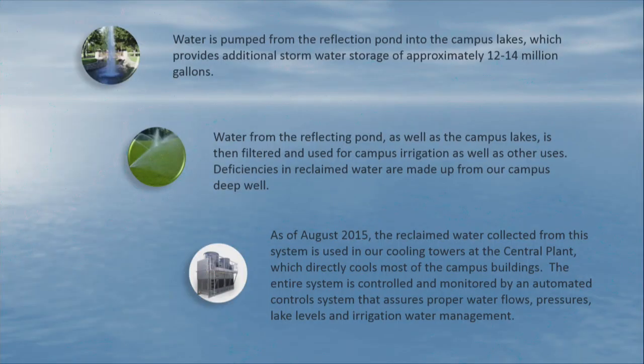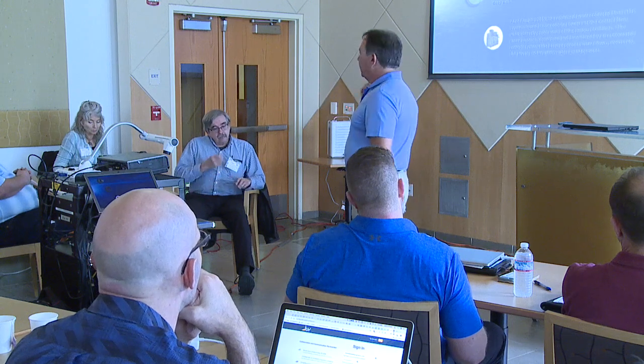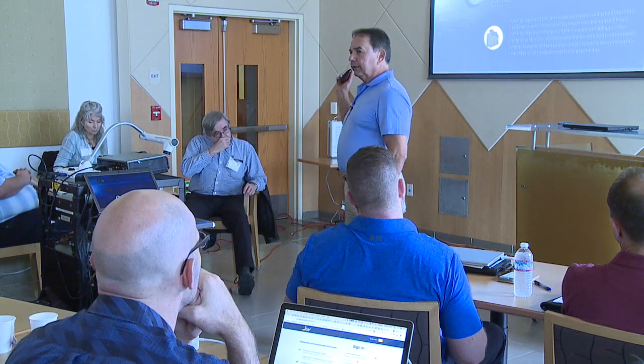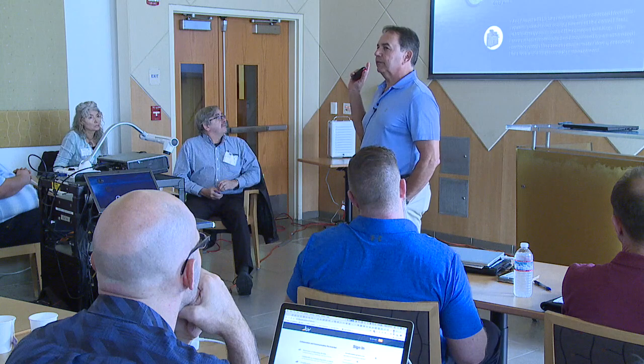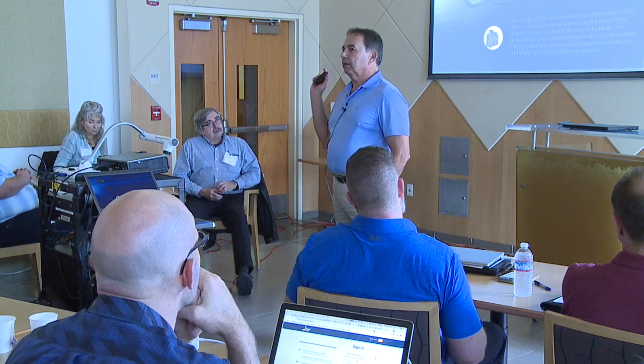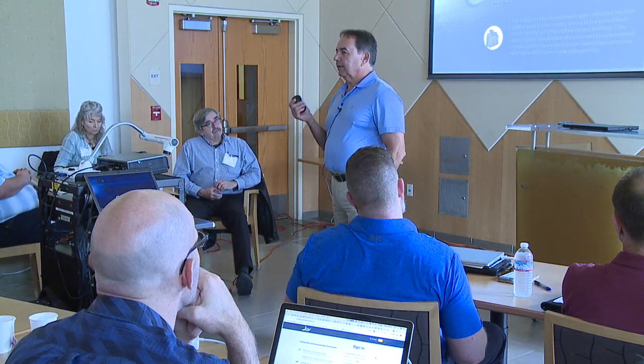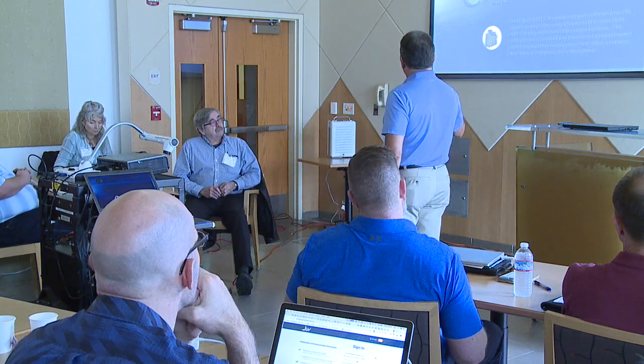As of 2015, the cooling tower — as you know, cooling towers use a lot of water — used about 5 million gallons a year of domestic drinking water. That's not only wasteful but also expensive. So we converted the tower to use reclaimed lake water instead. We had to do a couple of things to make it work, but we're now literally cooling 1.2 million square feet of campus using rainwater and lake water, which is really interesting.